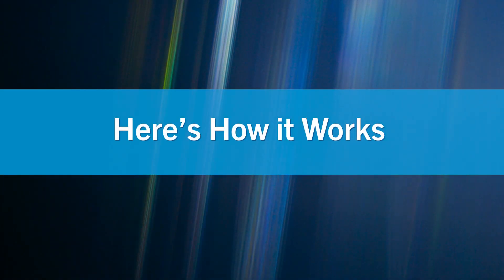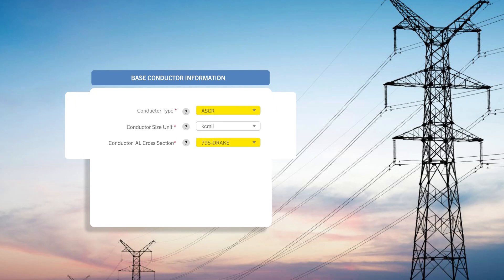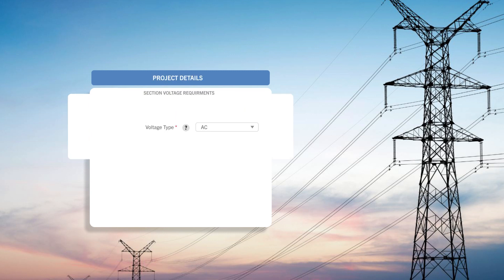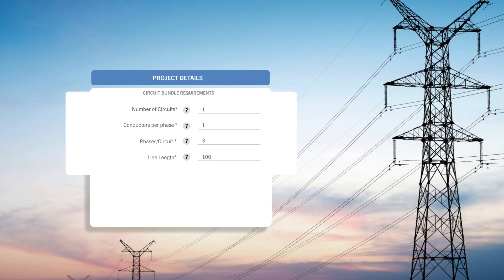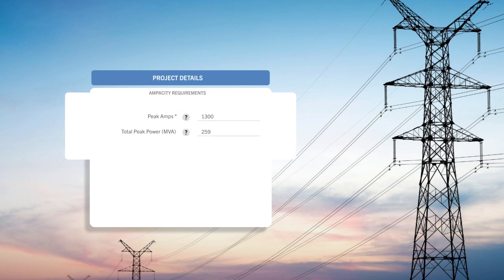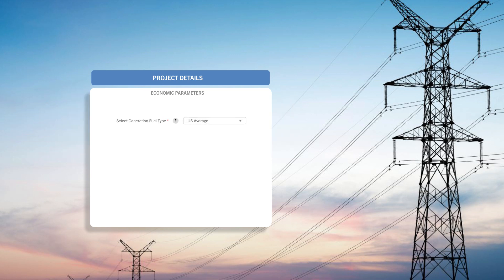Here's how it works. You simply select the conductor types and sizes of conductors you want to compare from drop-down menus, enter the desired line voltage, line length, ampacity, and operating assumptions and hit the calculate button.